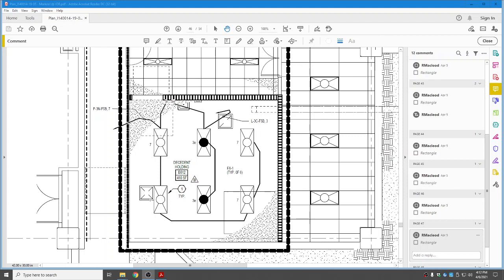Okay, shown here is my little remodel project, reflected new ceiling plan. You notice that we have a total of 6 lights in this space. We have 4 lights on normal power, and you can see here it's on panel 3N, F5B, circuit 7. And we have 2 lights that are denoted filled in, which suggests that it's on E power. And the home run shows us that we're going to panel L3C, which would be C being critical branch of the emergency system, F5B circuit 3.